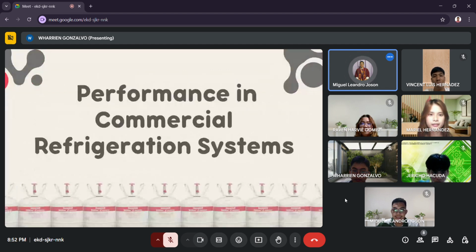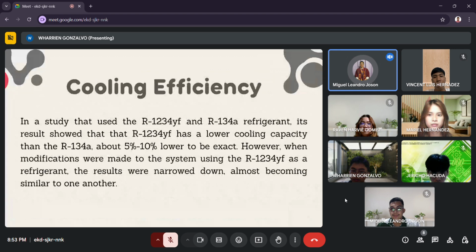Next, we move on to the performance in commercial refrigeration systems. First, we have the cooling efficiency. In a study that used the R-1234yf and the R-134a refrigerants, the results showed that R-1234yf has a lower cooling capacity than R-134a, about 5 to 10% lower to be exact. However, when modifications were made to the system using R-1234yf as a refrigerant, the results narrowed down, almost becoming similar to one another.